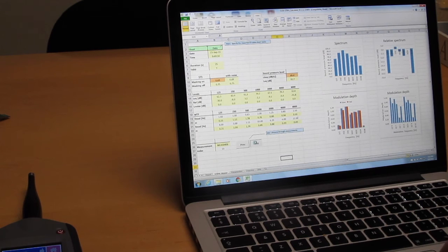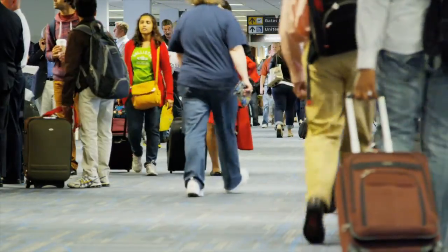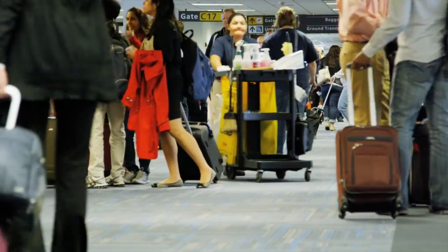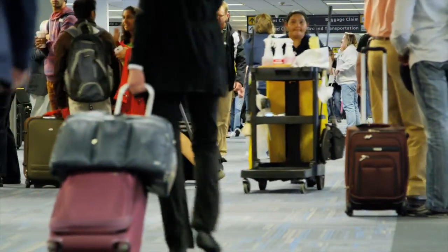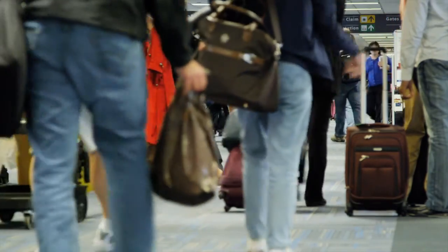The Excel tools can also be used for so-called post-hoc calculations. You will be able to add in ambient noise that was not physically audible during your measurements. This allows you to do your STIPA testing in an unoccupied building, but still incorporate the influence of all the noises that are present when the building is fully occupied.